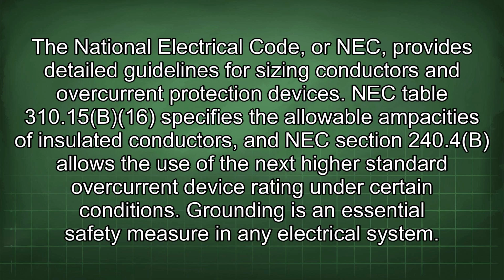The National Electrical Code, or NEC, provides detailed guidelines for sizing conductors and overcurrent protection devices. NEC Table 310.15(B)(16) specifies the allowable ampacities of insulated conductors, and NEC Section 240.4(B) allows the use of the next higher standard overcurrent device rating under certain conditions. Grounding is an essential safety measure in any electrical system.